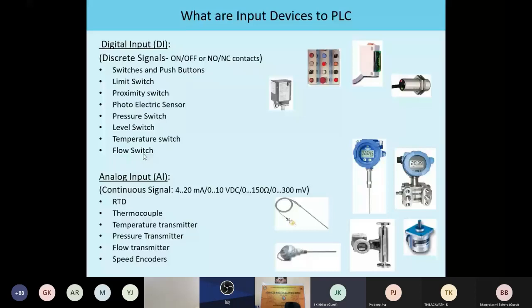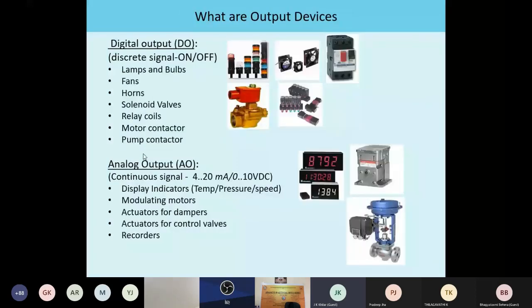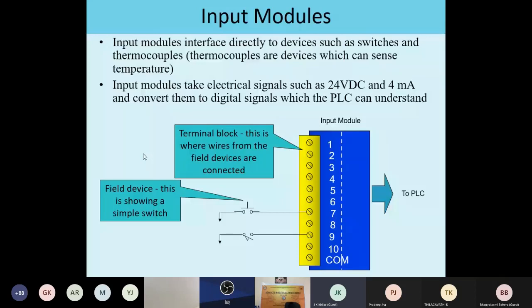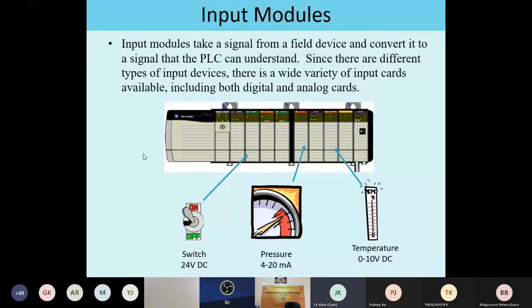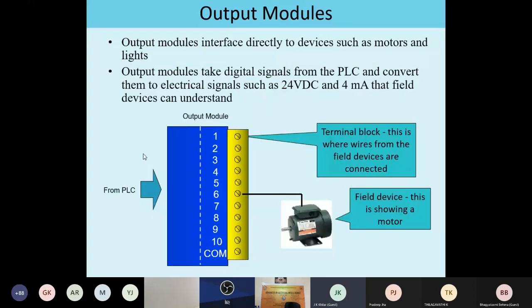Then outputs, similarly: to run a fan, to blow a horn, to open a valve, or to energize a relay coil, motor contactor, pump contactor, like this. These are known as digital outputs. Similarly, there are analog outputs. These are the input modules, showing how the input devices are connected to the PLC input card. Then after scanning the program, the outputs are connected through output modules to the devices or motors to operate. This is how the PLC system or SCADA system works inside our automation plant.